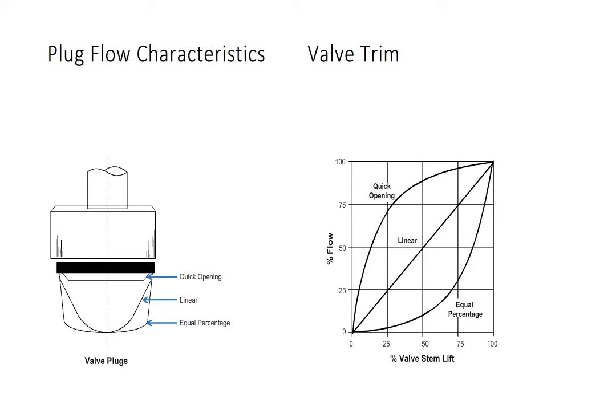Moving on to the linear plug on our graph, we can see that stroking the valve 25% results in a 25% flow rate. Stroking the valve stem 50% results in a 50% water flow and a 75% flow rate for a 75% valve stem lift or stroke. Clearly, we have a linear stroke to flow relationship.